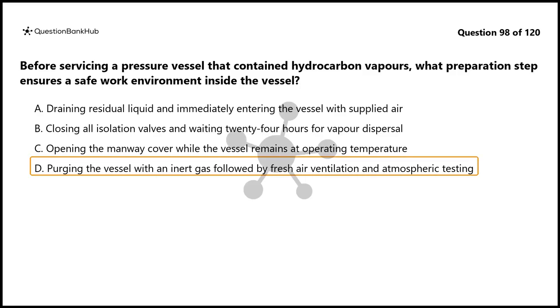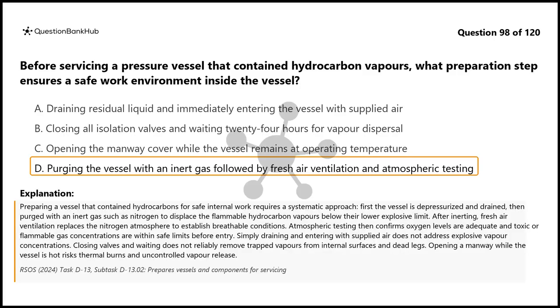The correct answer is D. Preparing a vessel that contained hydrocarbons for safe internal work requires a systematic approach. First, the vessel is depressurized and drained, then purged with an inert gas such as nitrogen to displace the flammable hydrocarbon vapors below their lower explosive limit. After inerting, fresh air ventilation replaces the nitrogen atmosphere to establish breathable conditions. Atmospheric testing then confirms oxygen levels are adequate and toxic or flammable gas concentrations are within safe limits before entry.